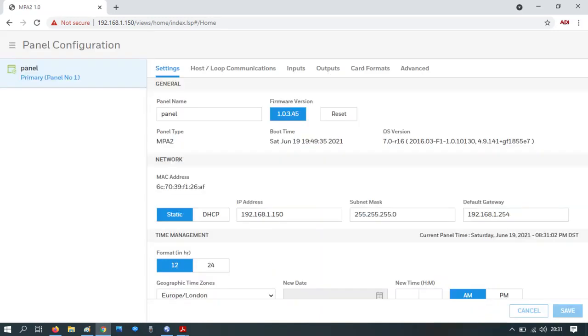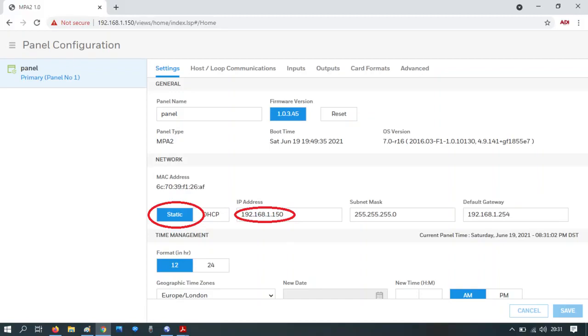In the panel configuration window, you can set the IP address of the device. It's strongly recommended you set this to a static address. At this point you can change the IP address in the IP address field to change it to an IP address that suits the installation.